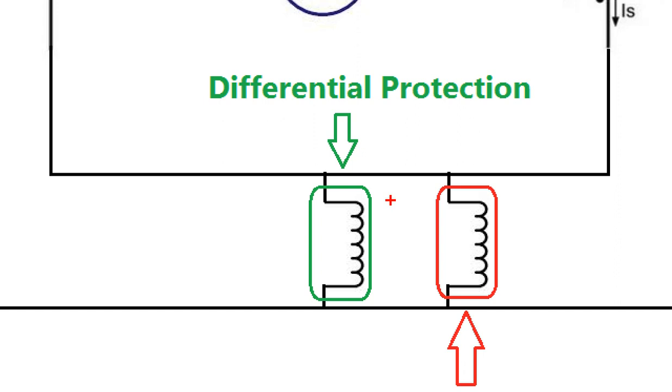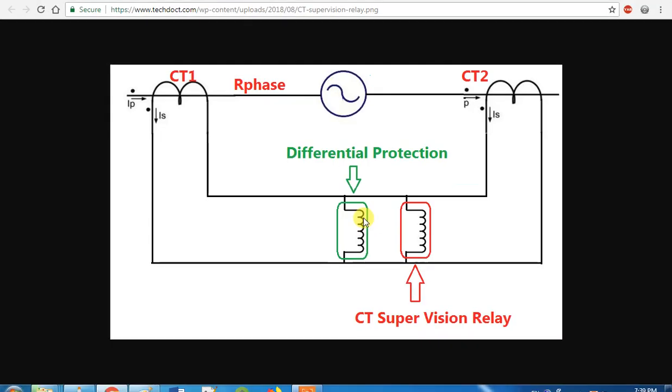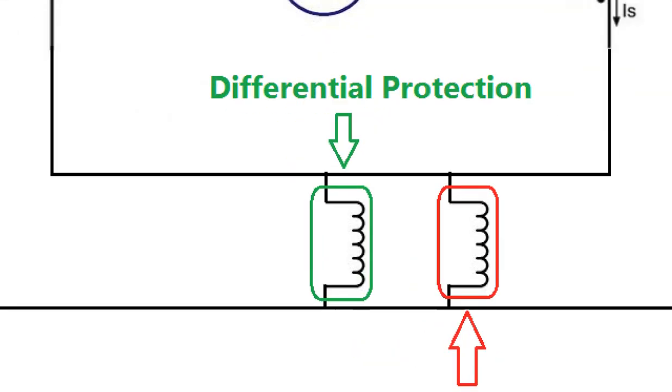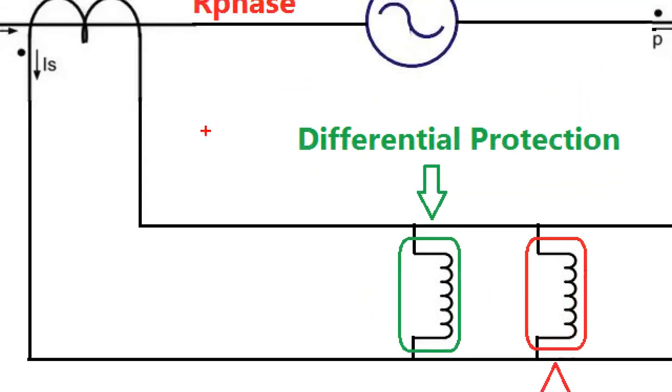We need to improve the stabilizing resistance. But we need to calculate the stability resistance. So if there is a fault current, it's 10kA. That CT is saturated. So how did we calculate the stabilizing resistor and install the stabilizing resistor?